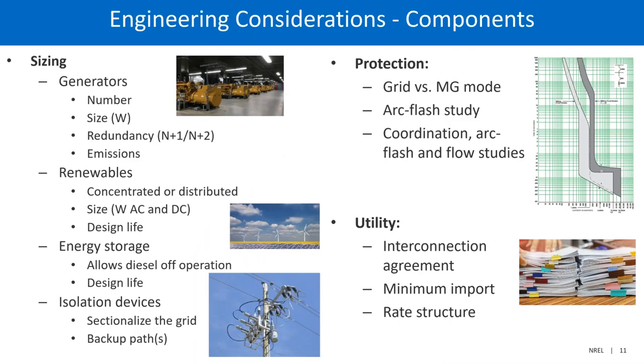All right, so some of the engineering considerations that go into the design of a microgrid. For the sources, there are a lot of different components that you need to figure out. If your source of power is going to be generators, you need to determine not only how many kilowatts they are, but how many of them you have. It can sometimes be more resilient to have, say, 5 one-megawatt generators than 1 five-megawatt generator. So there are a lot of trade-offs that way.